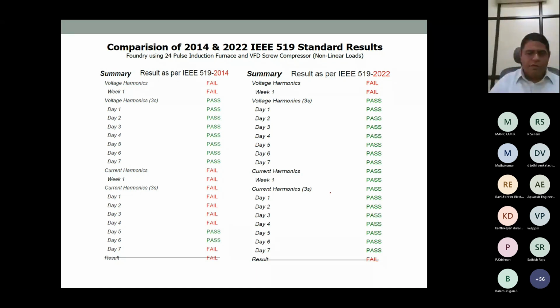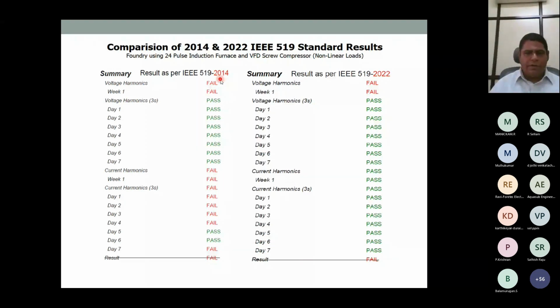So as per 2014 norms, let us not worry about the voltage harmonics, which my report shows as fail. It shows a fail for a different reason. There are some industries who are dumping harmonics, and because of that it is failing. It is not because of our own loads. Our own loads are complying. So voltage harmonics is not our purview. It is the purview of both of us, that is the DISCOM and the consumer. It is a joint responsibility. So this fail should not be considered.